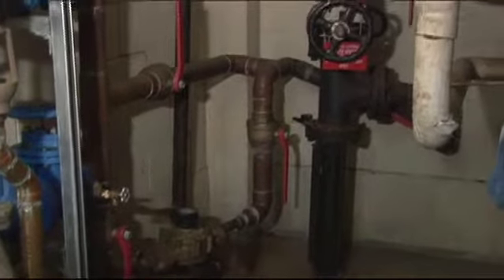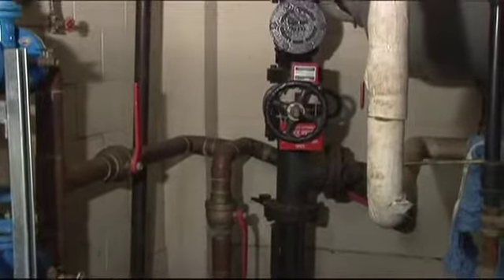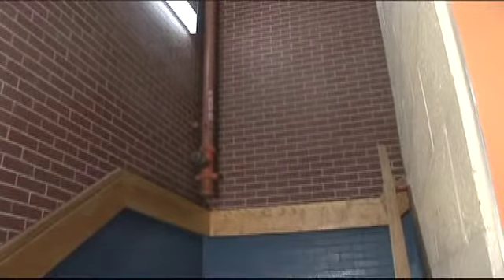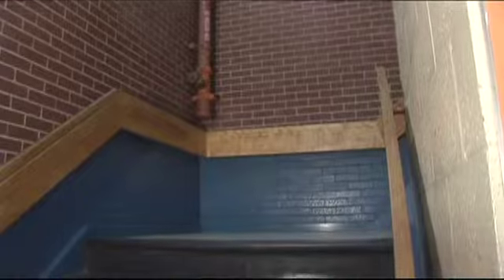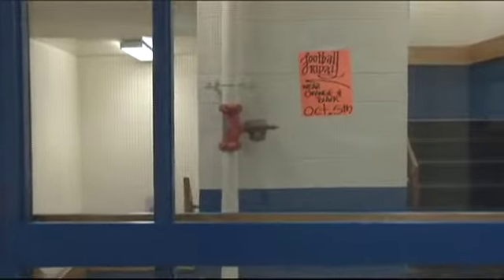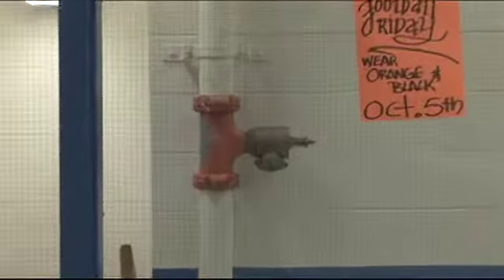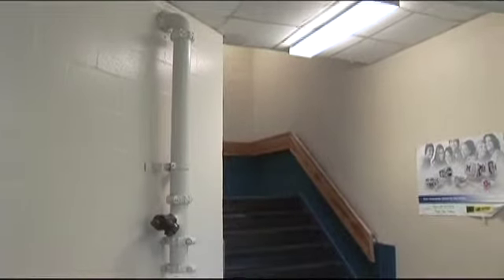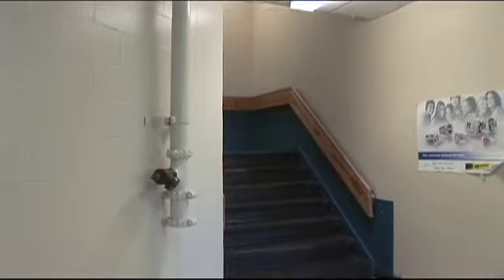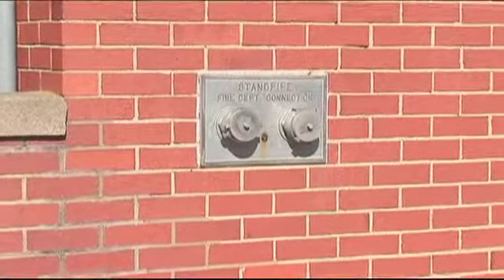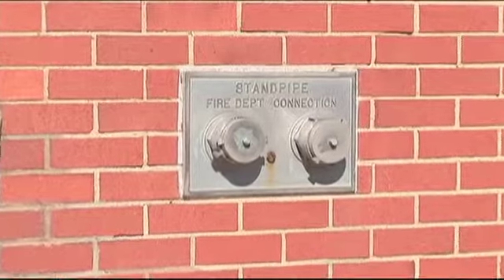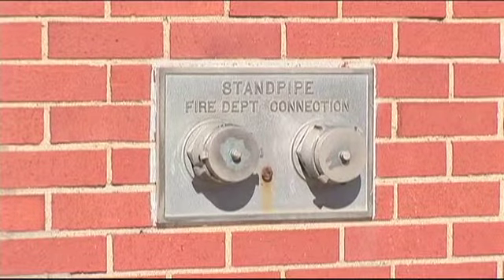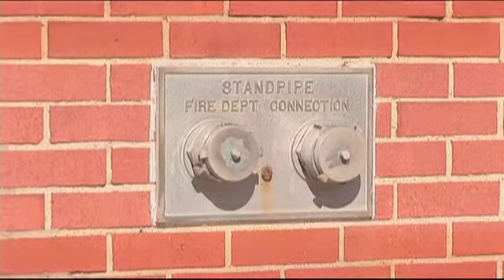A standpipe system is a system of piping, valves, outlets, and related equipment designed to provide water at specified pressures and is installed exclusively for the fighting of fires. Now, most standpipes are located in the intermediate stairwell landings and are fed off the main water supply. Most zone valves are equipped with tamper switches and they're monitored at the main fire alarm panel. The system can also be boosted by a fire department pumper truck via a fire department connection located outside the building.